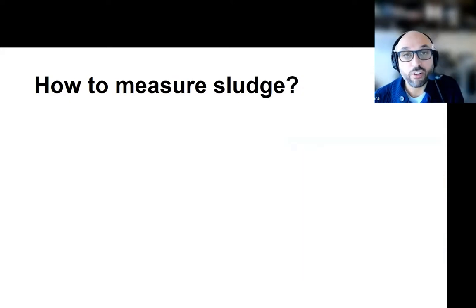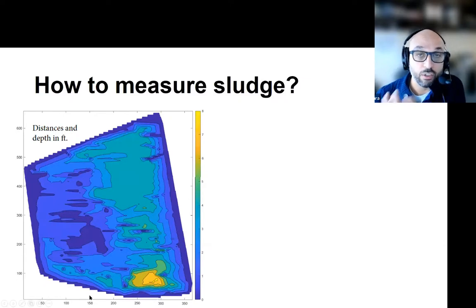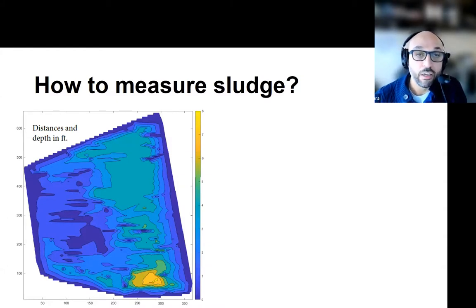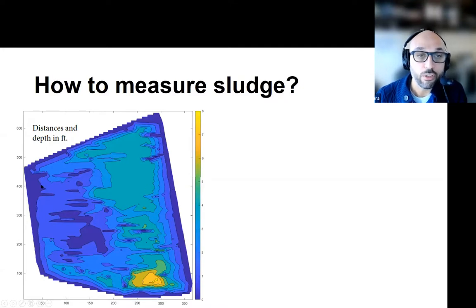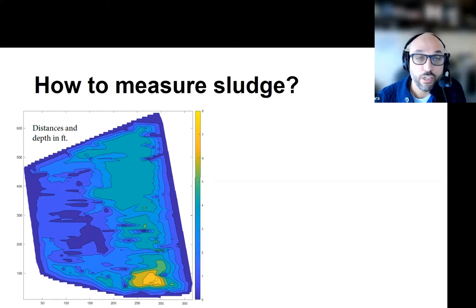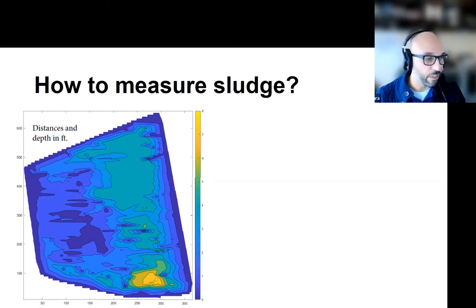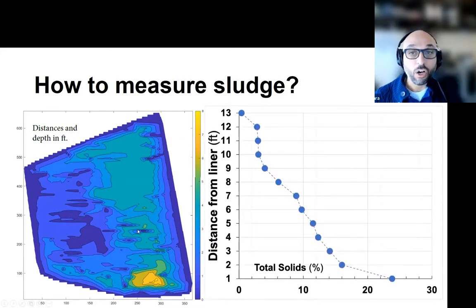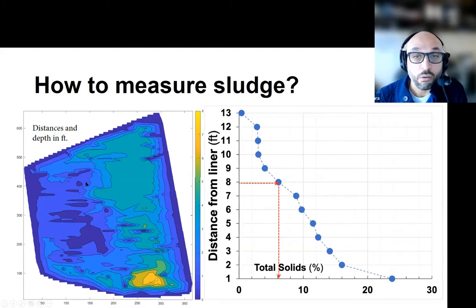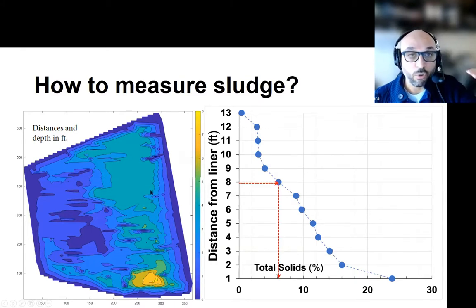Using those two pieces of information - the volume of sludge and the concentration of nutrients or solids content - you can start to develop plans for sludge utilization. What you're seeing on the screen is the product of a remote control boat that has scanned a lagoon structure. The color represents the depth to that sludge: the lighter color is deeper areas, whereas the darker color represents a shallow distance, which means larger sludge accumulation. On the right hand side, this is the result of collecting a complete sample of the lagoon foot by foot and determining the solids in these samples. With those two, we can determine at what depth the sonar is indicating sludge presence.